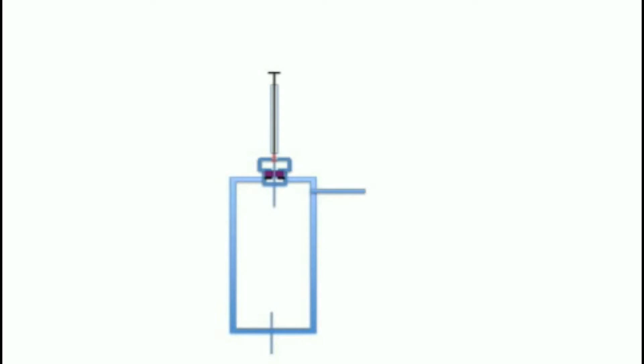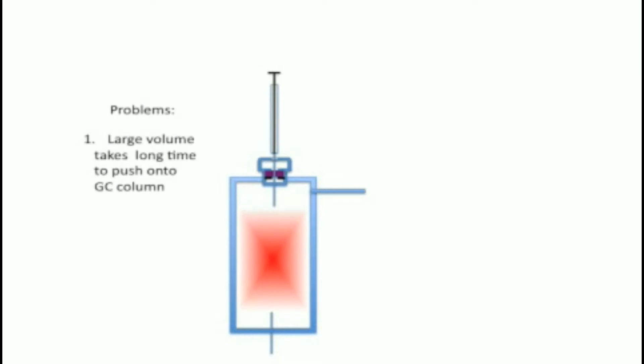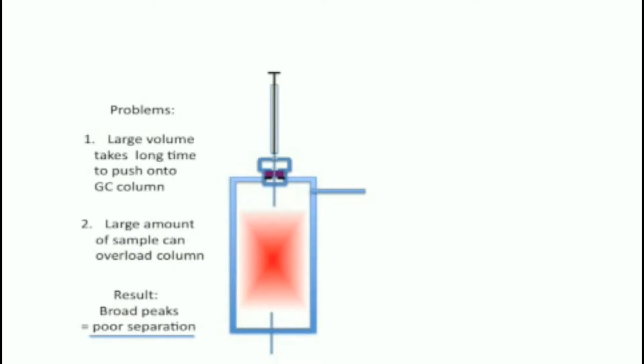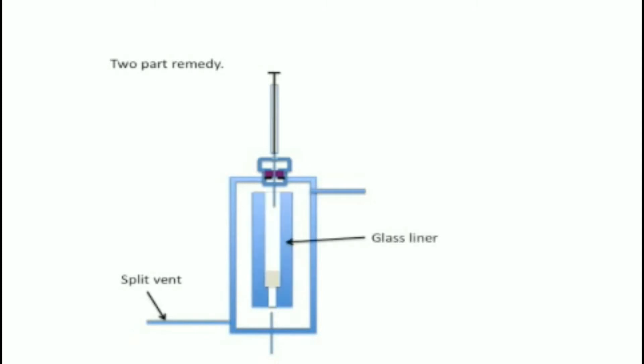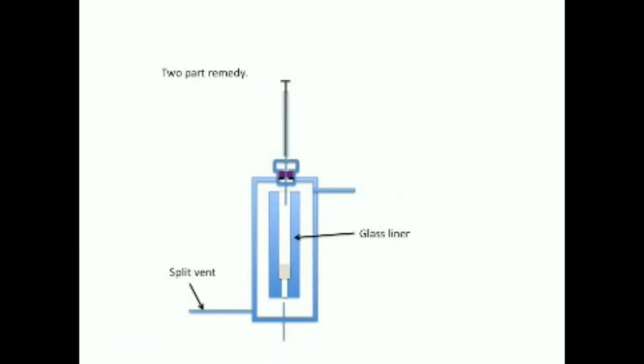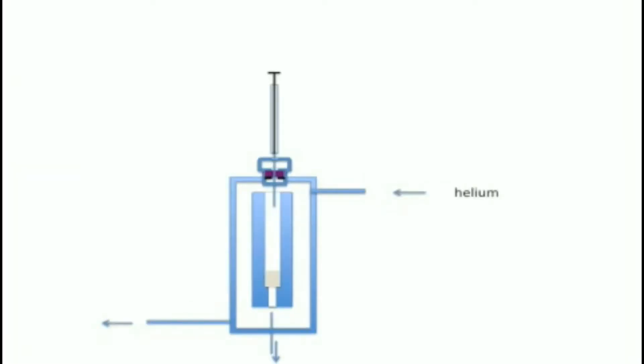If we let the sample gas fill the entire injector, it will take a long time and a large volume of helium to push it all onto the column. Furthermore, even microliter amounts of sample will overload the stationary phase on the capillary. The most common remedy is known as a split injection. We introduce another opening at the bottom to allow gas to escape — this is known as the split vent. We also confine the sample to a smaller volume by inserting a glass liner, which often contains a small bed of silica particles coated with stationary phase at the bottom. The particles enhance vaporization and help focus the gases. As sample vaporizes inside the glass liner, it has two ways to escape: a very small portion goes down the capillary while a much larger portion goes out the vent.